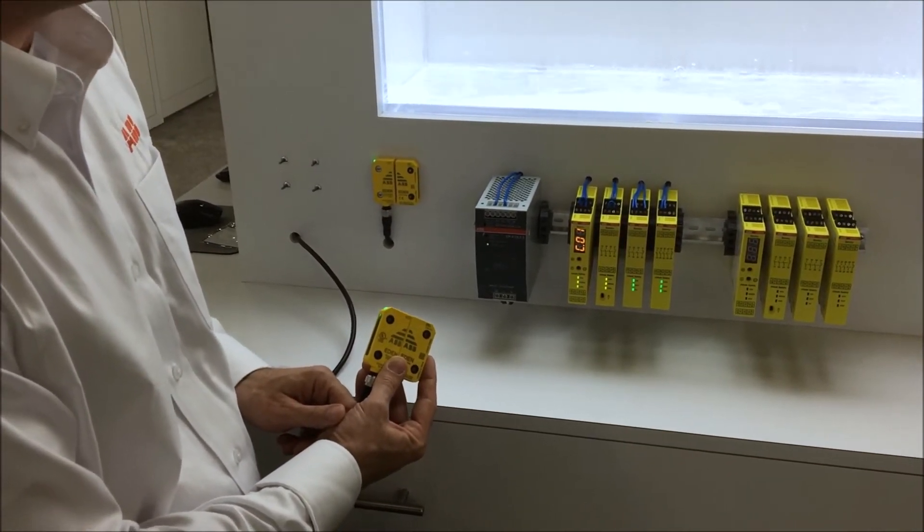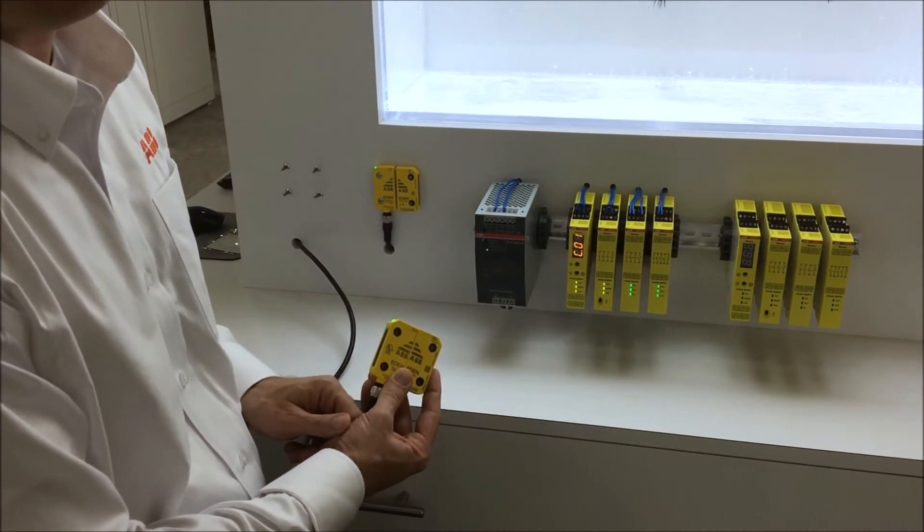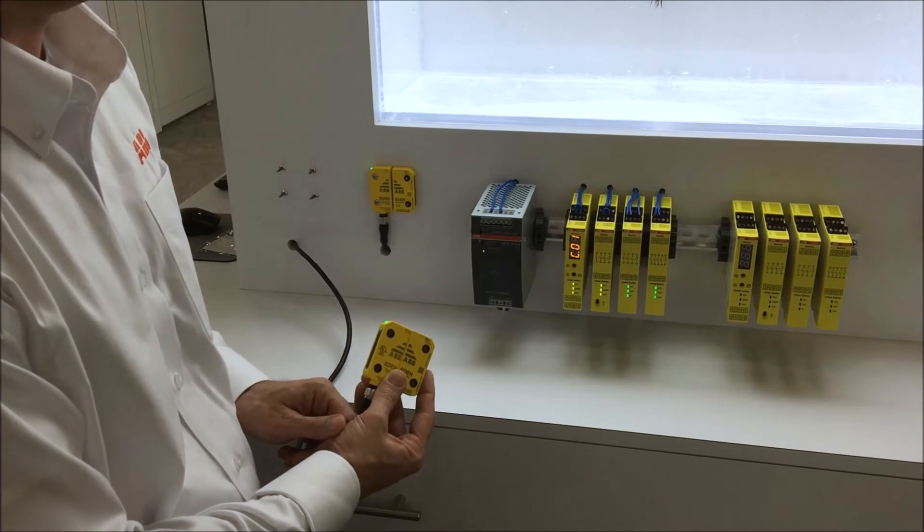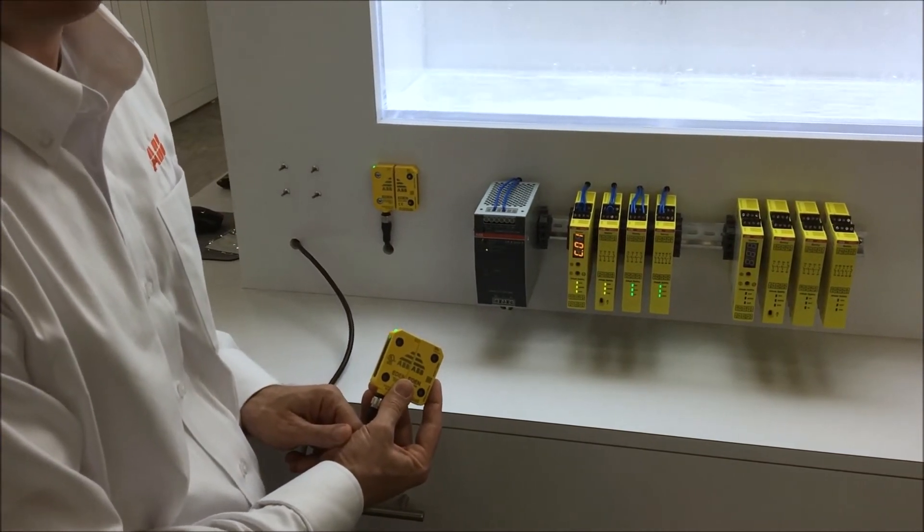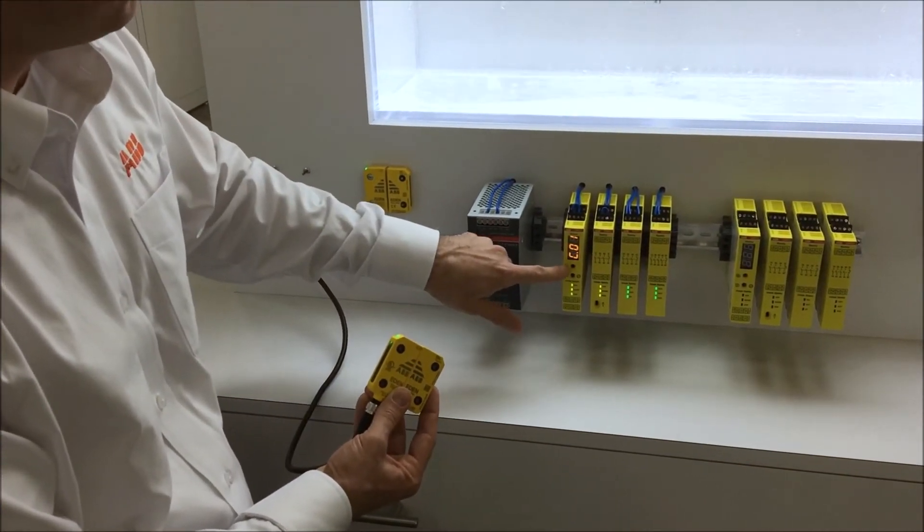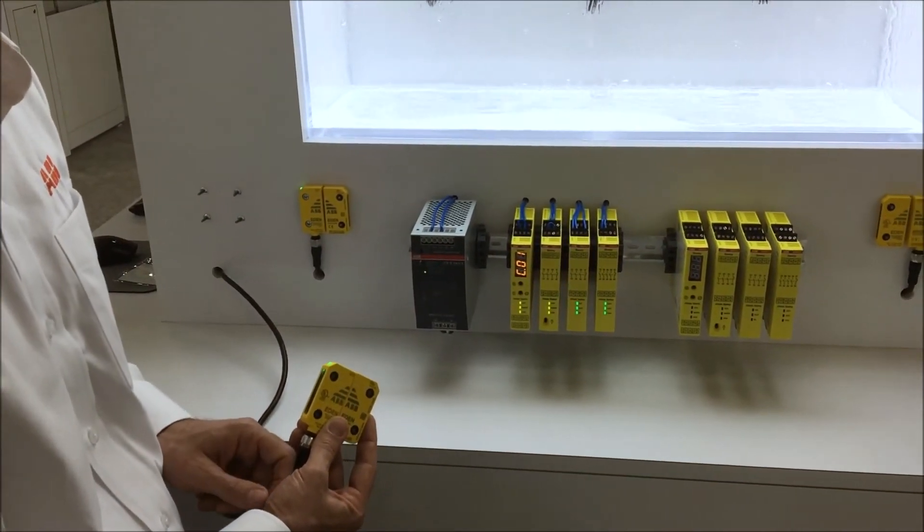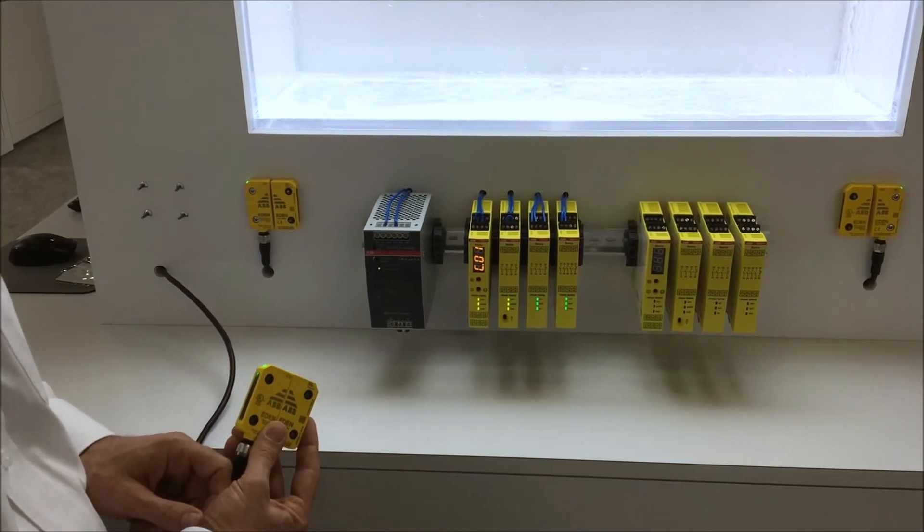It gives us the ability to do soft stops or delayed outputs, delayed on outputs, timed reset or time bypass functionality. Simply by selecting the functionality through two push buttons on the front of it, we can enter the program mode and select the features and benefits we want in that safety relay.